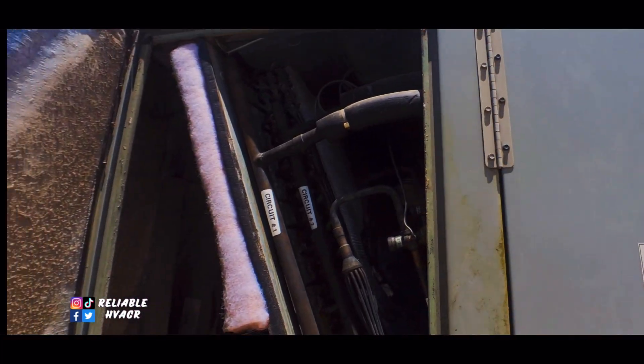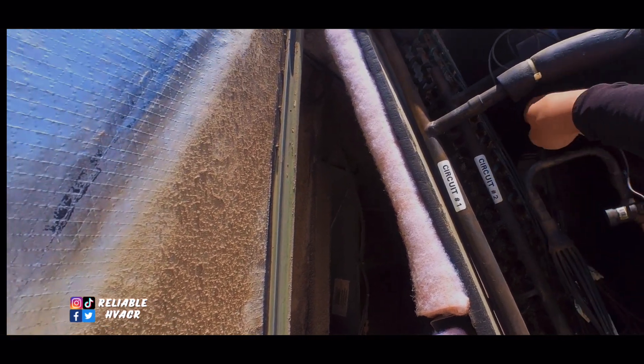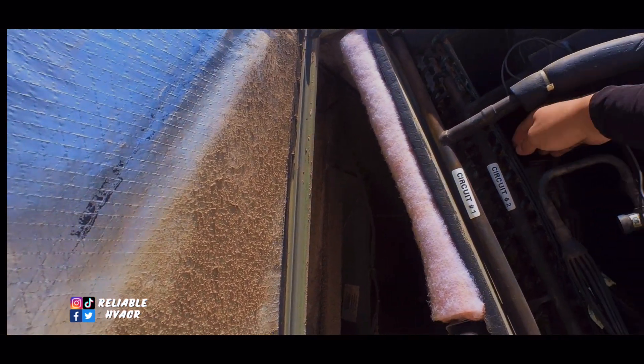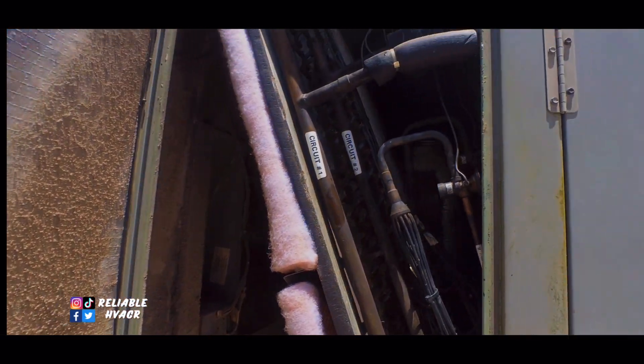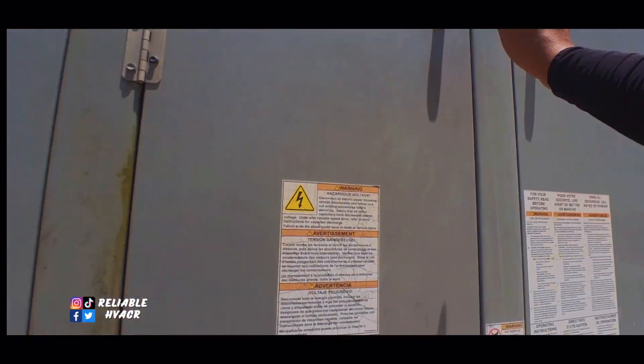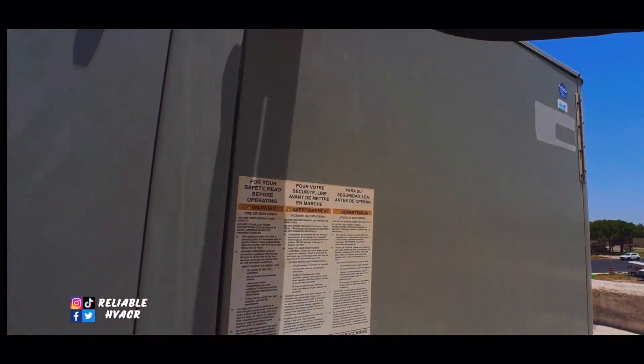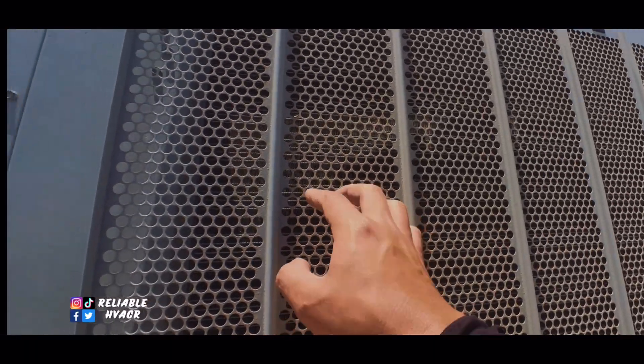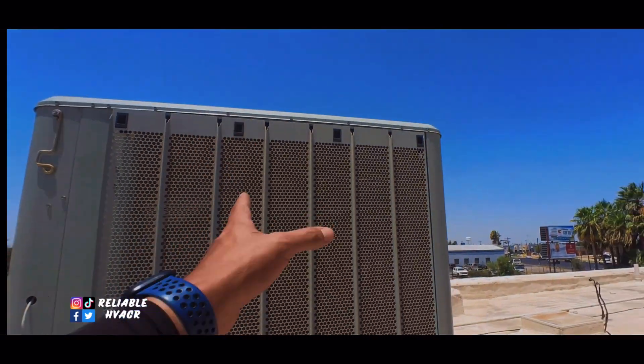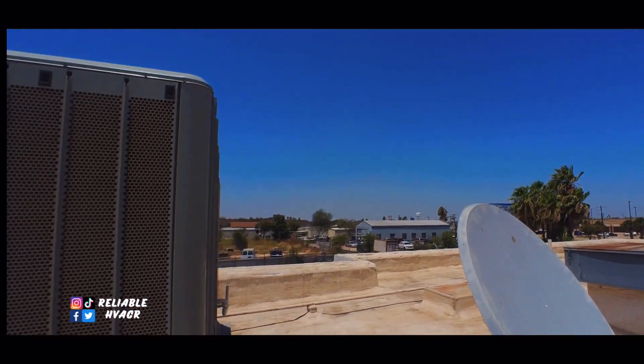They said the back was hot. It's not doing too well. The evaporator is cold though. Suction lines are slightly cold, not great. So that means all the way to the compressor is just cold - it's not sweating or anything. Micro channels - they look like they are dirty. I can still see through them and stuff, but they look like they're covered in dust and dirt.